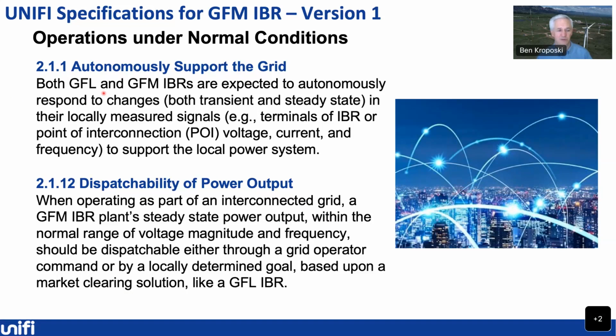without any type of commands. We also want a dispatchability of power output. This is something that we're seeing more often now, this ability to send a command out to these devices so that you can dispatch power up or down, for example, curtailing solar or wind when you have too much of that on the system. But this is going to be more of a dispatch command. Again, grid following inverters should be starting to have this capability, but grid forming ones also.